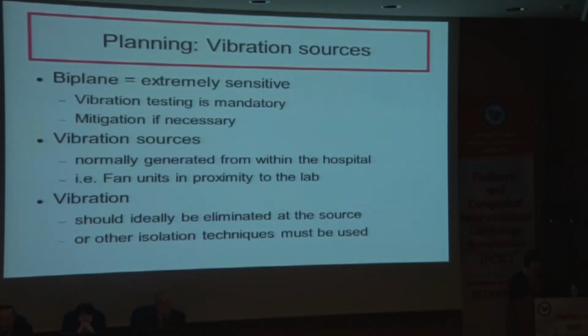Specifically about the vibration sources, it's important to keep in mind that especially the biplane systems are extremely sensitive to vibration, and vibration testing is mandatory, and mitigation must be done if necessary. And the most important vibration sources are normally generated from within the hospital, for example, your fan units in proximity to the lab. And these sources should ideally be eliminated at the source, or otherwise other isolation techniques should be used.